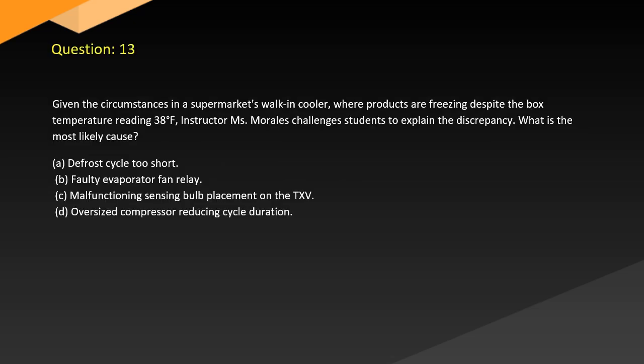Question 13. Given the circumstances in a supermarket's walk-in cooler where products are freezing despite the box temperature reading 38°, the instructor challenges students to explain the discrepancy. What is the most likely cause? A. Defrost cycle too short. B. Faulty evaporator fan relay. C. Malfunctioning sensing bulb placement on the TXV. D. Oversized compressor reducing cycle duration.